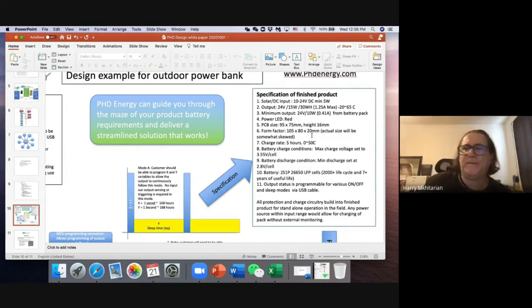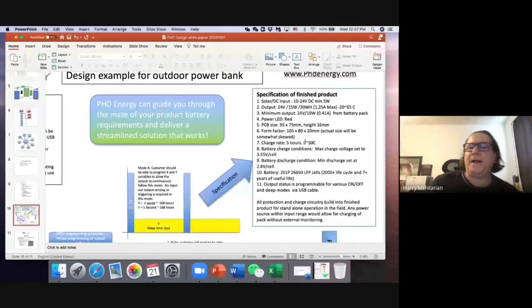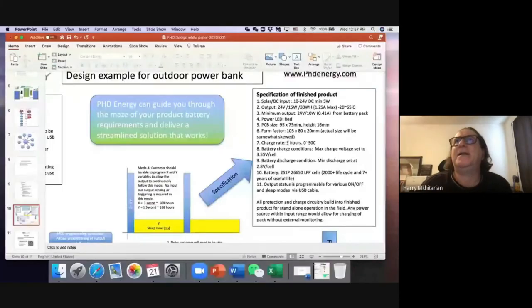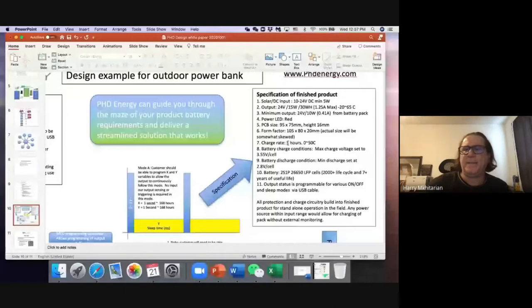We had charge control over 5 hours, and we control the charging from 0 to 50 C. Typically we would do 45, but because this was outdoors, we made it 50 C. The charge rate was low enough in this case that we could do that. Typically if you have a high charge rate, we recommend 45 C as the higher temperature cutoff. But this battery capacity had a lower C rating, so we were able to do that for them.